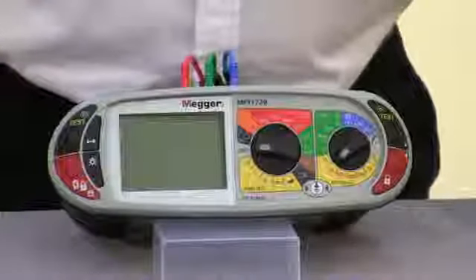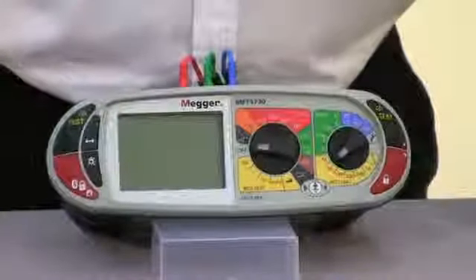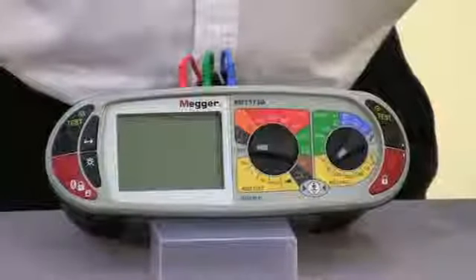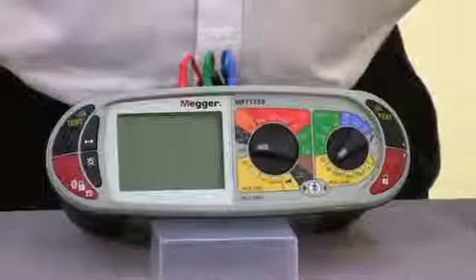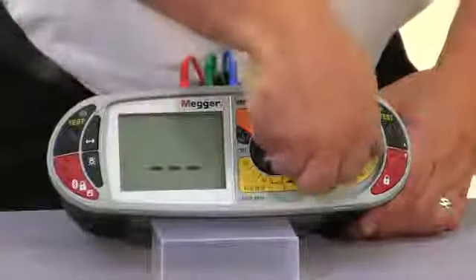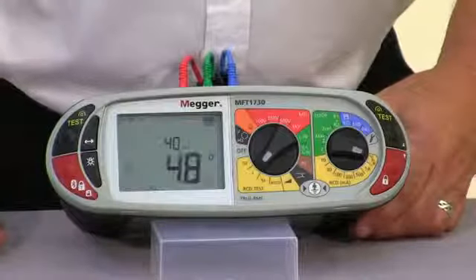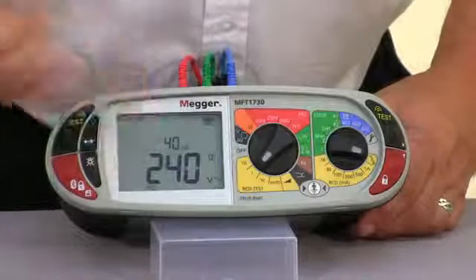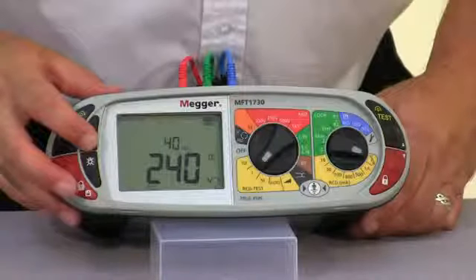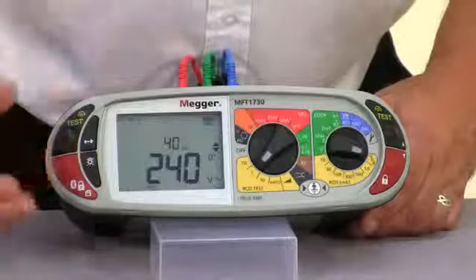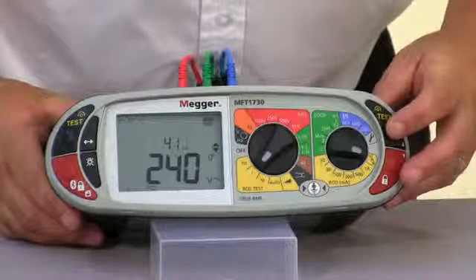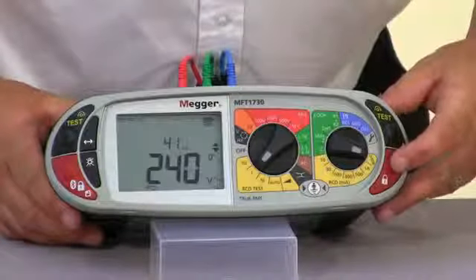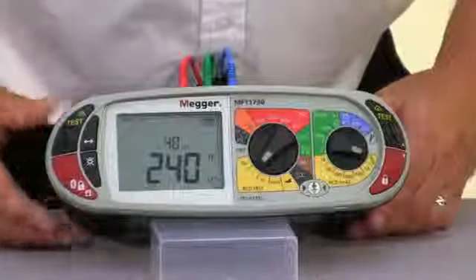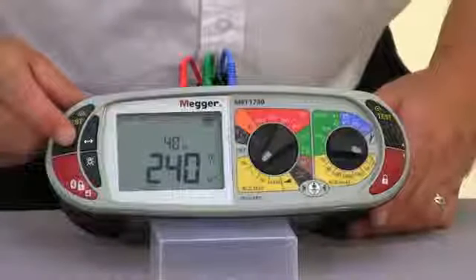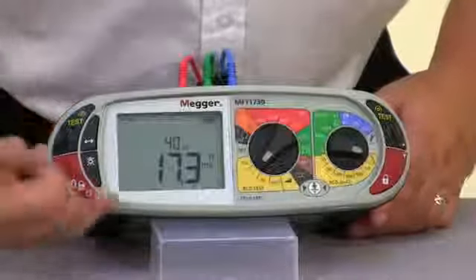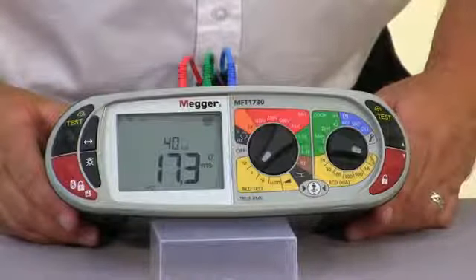The variable RCD test that we have available on the MFT1720 and 1730 will allow you to dial up a non-standard RCD trip current. So if I show you, for example, a 40 milliamp RCD test, as you can see it's actually defaulted to that, but what we can do is by selecting the function key, we have our up and down arrows, and using the up and down you can see quite clearly it's very simple to select the value of the test that we want. So turning the selection off, pressing the test button, which will do a times 1 test, and as you can see we've got a reading of 17.3 milliseconds.